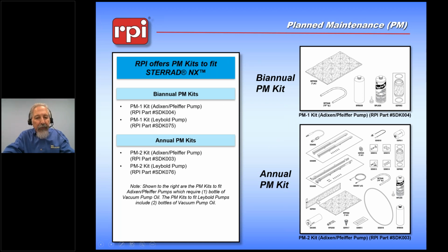We also have an annual kit, it's called the PM Kit 2, that also contains the biannual kit, which allows you to do the oil change, and includes things like the rails that are within the chamber, which will decay from the exposure to the hydrogen peroxide. We get a new catalytic converter that will break down over time, a new UV lamp, which we want to make sure stays working through the entire year, and a door gasket.